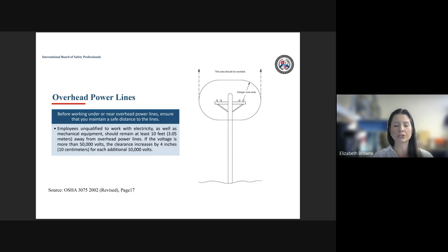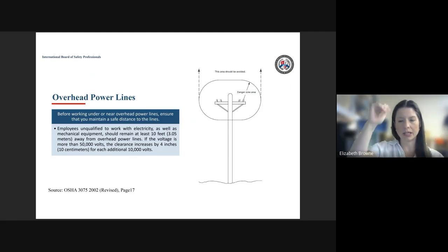And then there's a table in the OSHA standards that tells us that if we're over 50,000 volts, or I'm sorry, 50 kV, then the clearance needs to increase by 4 inches or 10 centimeters for each additional 10,000 volts. And that area is, we're talking about from the ground up, staying at least 10 feet away. This is very serious and something we should be very aware of.